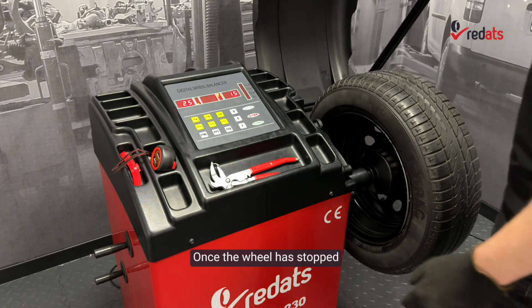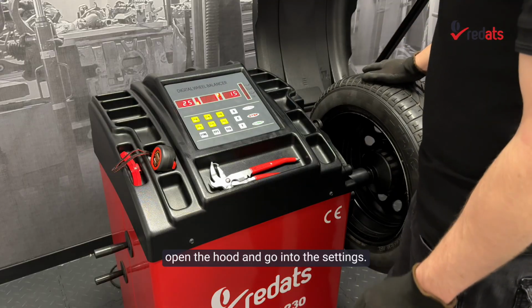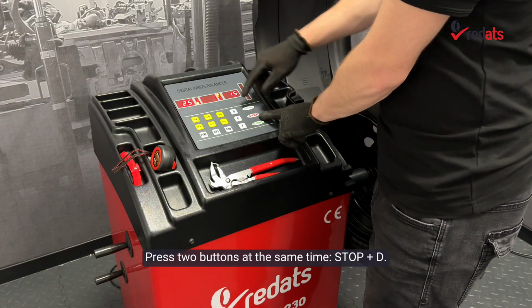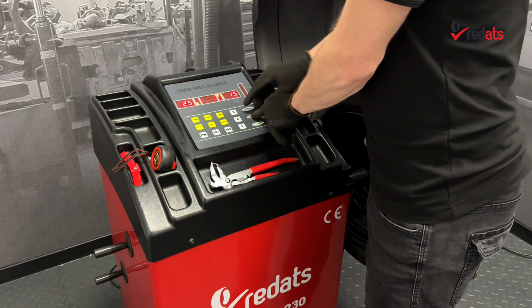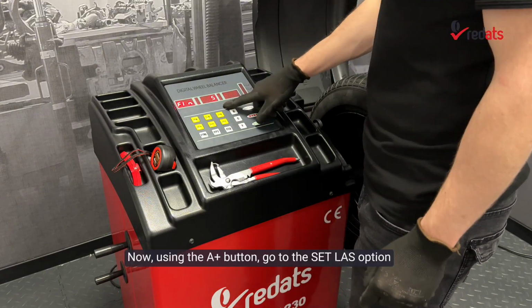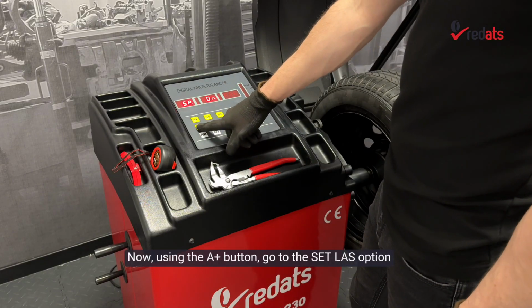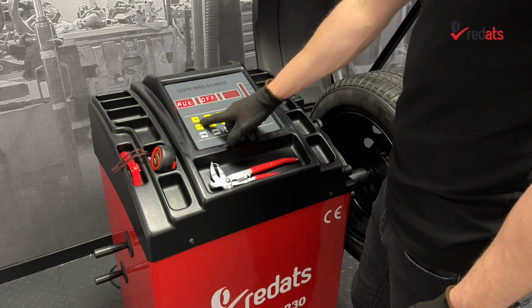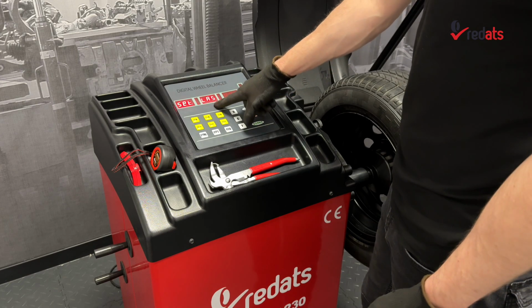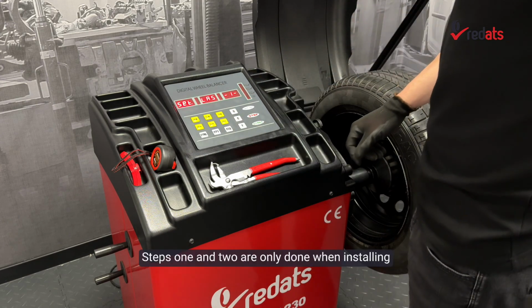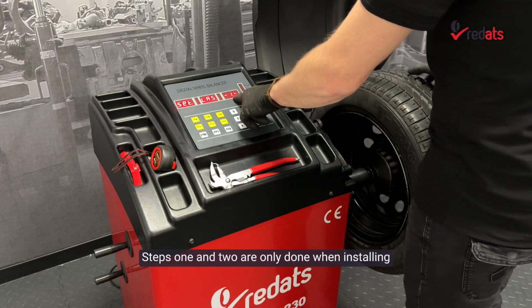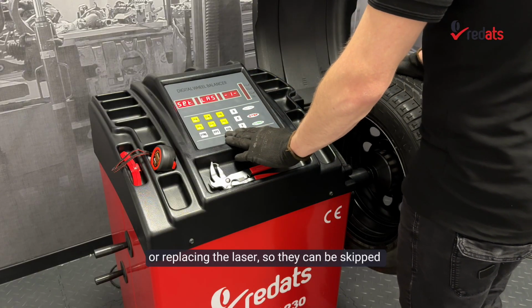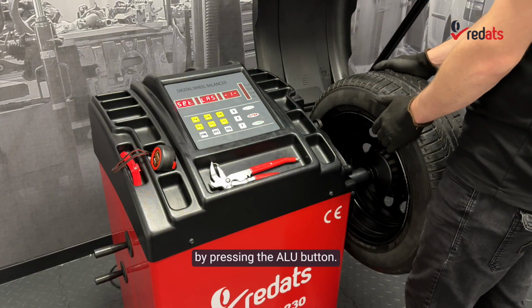Once the wheel has stopped, open the hood and go into the settings. Press 2 buttons at the same time, stop plus D. Now, using the A+ button, go to the Set LAS option and press B+. Steps 1 and 2 are only done when installing or replacing the laser, so they can be skipped by pressing the ALU button.